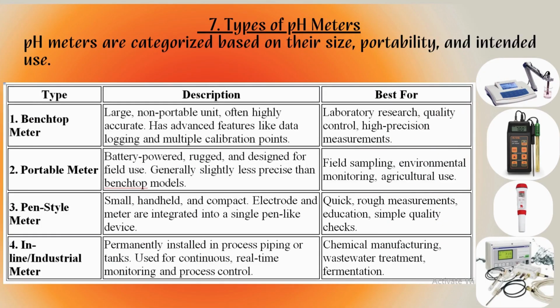Now the types of pH meters. pH meters come in various designs to suit different applications. The first one is benchtop meters. These are the standard laboratory-grade instruments we have discussed, offering the highest accuracy and advanced features like data logging and multiple calibration points. The second type is portable or handheld meters, which are battery operated and designed for field use such as environmental testing, often built to be durable and waterproof. Pocket testers or pH pens are the simplest, pen-sized versions used for quick measurements where high precision is not required. The choice depends entirely on the required accuracy, portability, and the environment of use.